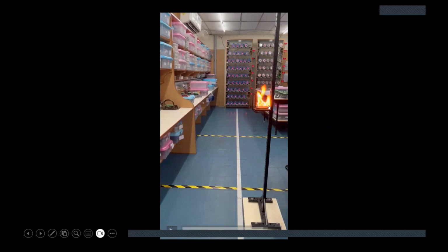So here we have a 50 mm flame and the distance is 6 meters. And you can see all the detectors which are mounted in different angles, and even on the right side, we have different types of detectors. And here, each of the detectors has different viewing angles. And within a few seconds, you could see the entire detector is detecting a single source of fire.